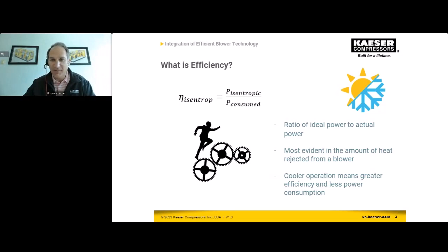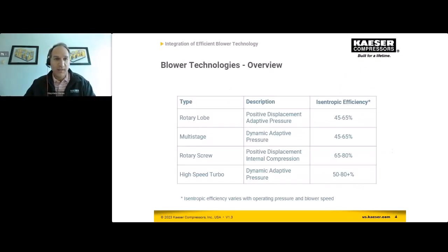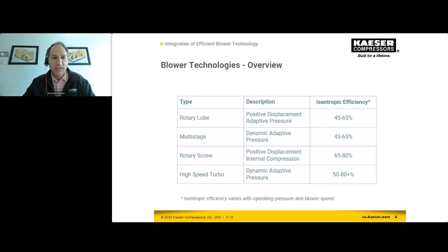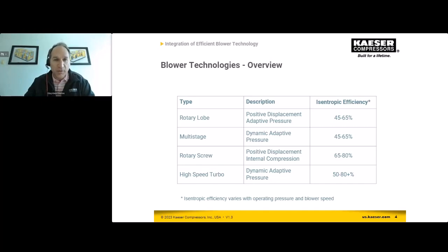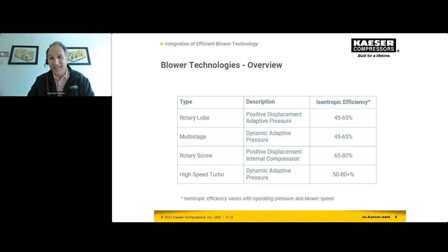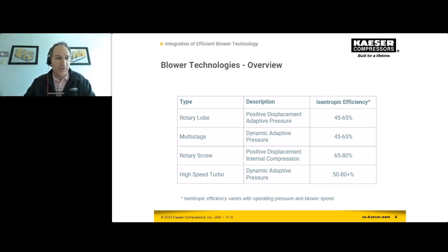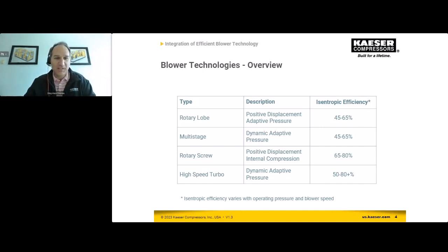When we talk about efficiency, less power consumption is clearly a benefit as well. Now let's look at the blowers most commonly used in the wastewater industry. We at Kaeser make some of these. We have the rotary lobe — a positive displacement, roots-type blower — which has been around since the Victorian era and operates at 45% to 65% isentropic efficiency. Then we have the multi-stage, which is very popular in the United States. If you stop at 10 wastewater plants, at least 50% or more will have a multi-stage machine.